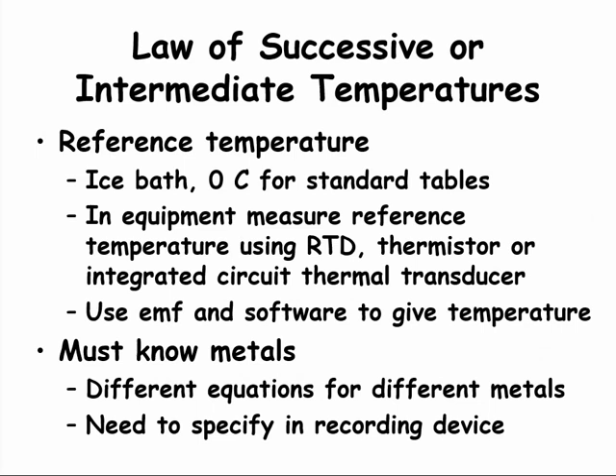As mentioned before, if you have a simple two-wire circuit and need an external reference temperature, the standard reference temperature is an ice bath. In the old days, before modern electronics, there were standard reference tables that listed the EMF for each temperature, typically down to a hundredth of a degree Celsius. With modern electronics, we measure the temperature of the isothermal bar inside the meter with an RTD, thermistor, or an integrated circuit thermal transducer. Then we need to tell the meter which metals you are using so that the meter uses the correct equation to calculate temperature based on EMF measured.